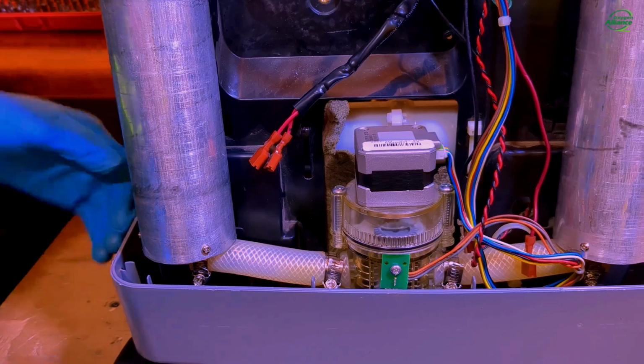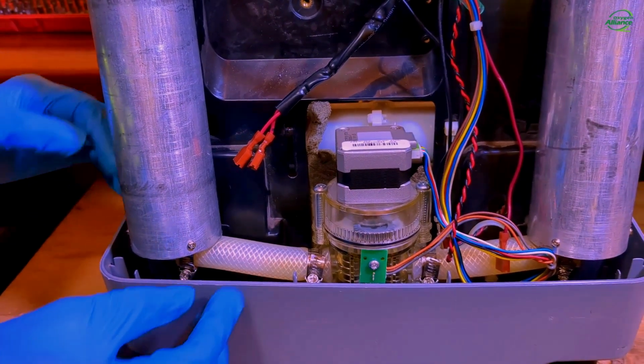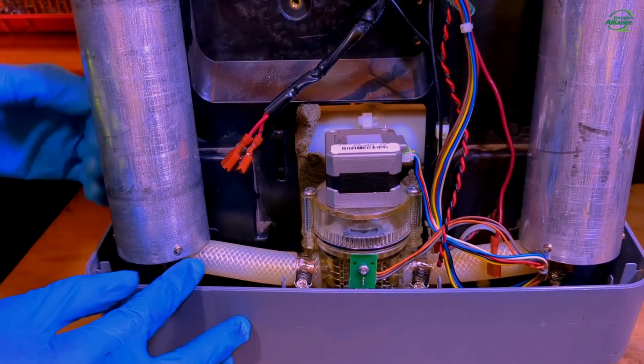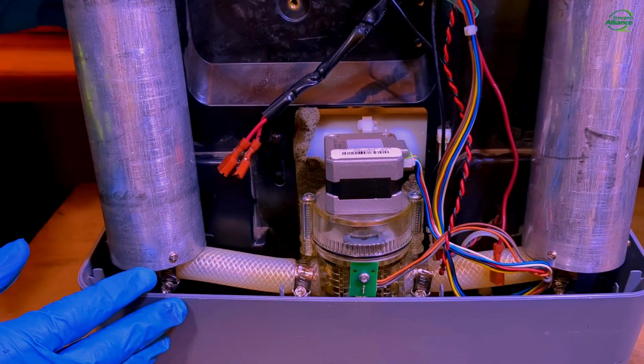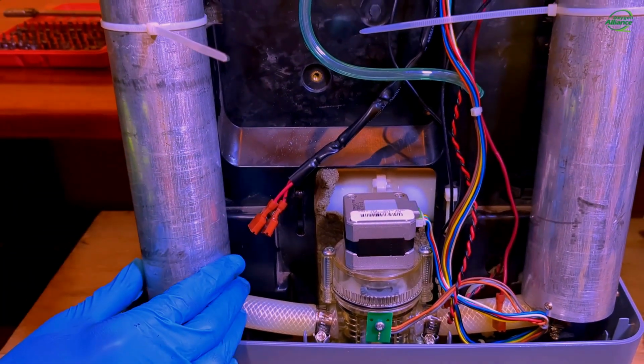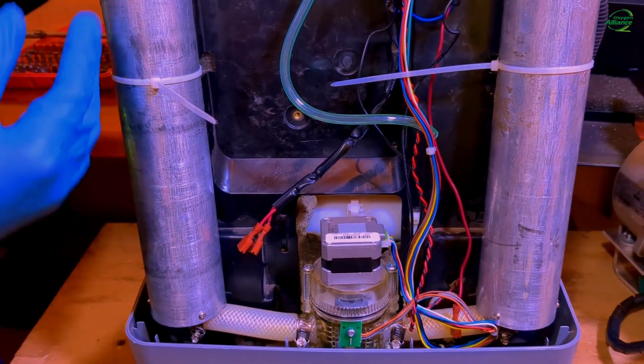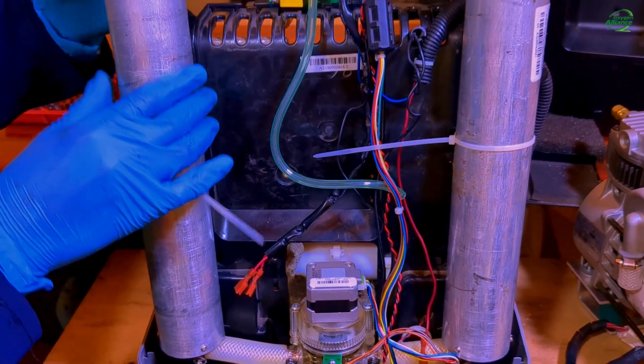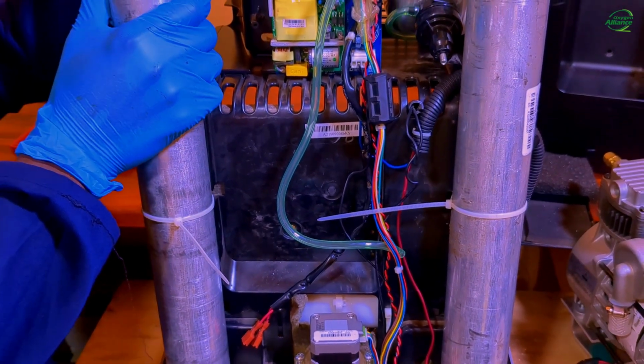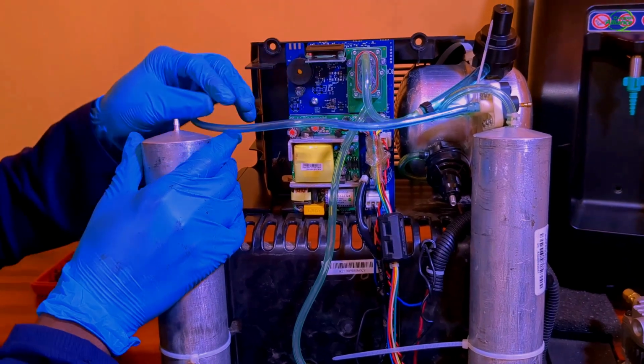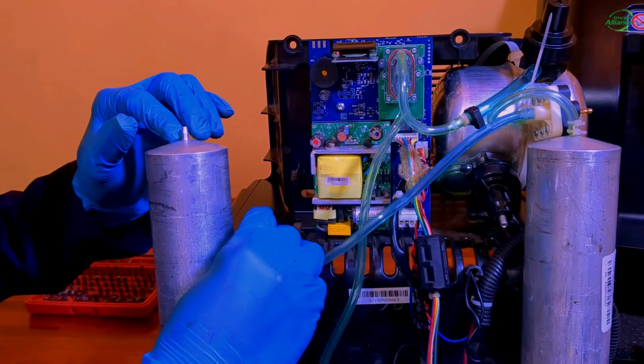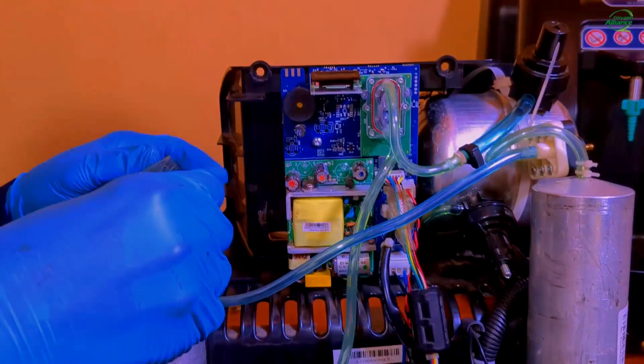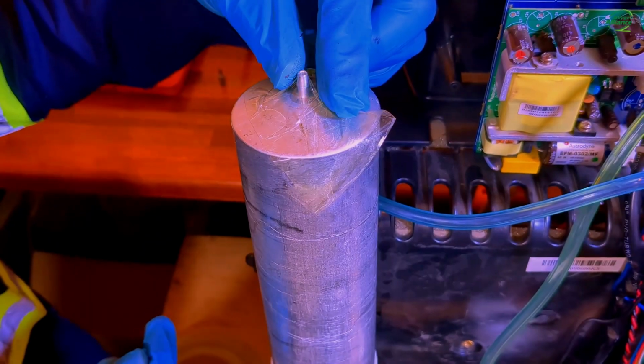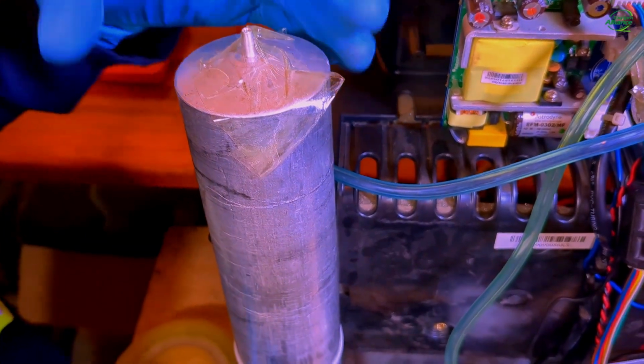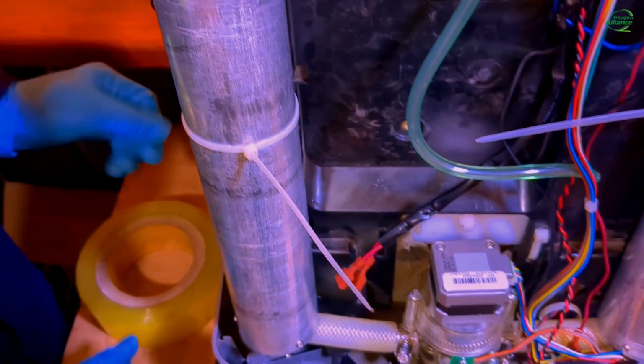port. So I am going to show you how to remove the rotary valve. In order to remove the rotary valve, we need to also remove the sieve beds. To remove the sieve bed, firstly we need to disconnect this tubing, and remember to tape the opening. We tape the opening to avoid exposing zeolite to moisture.